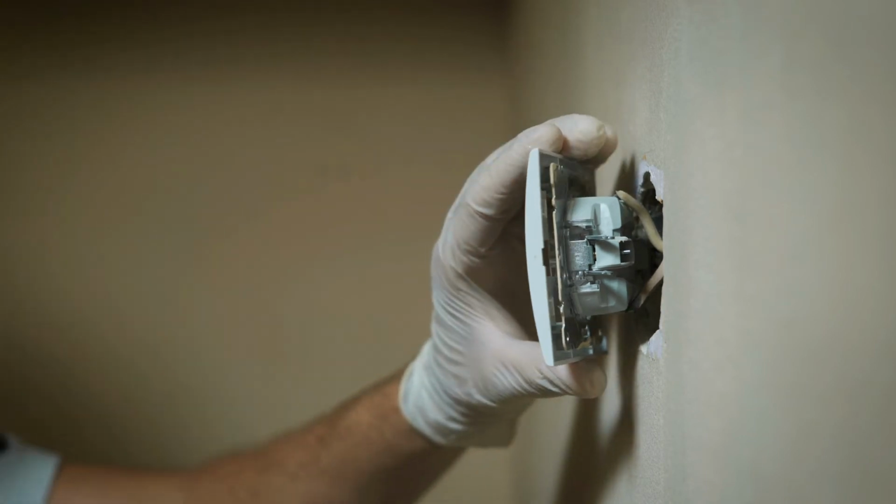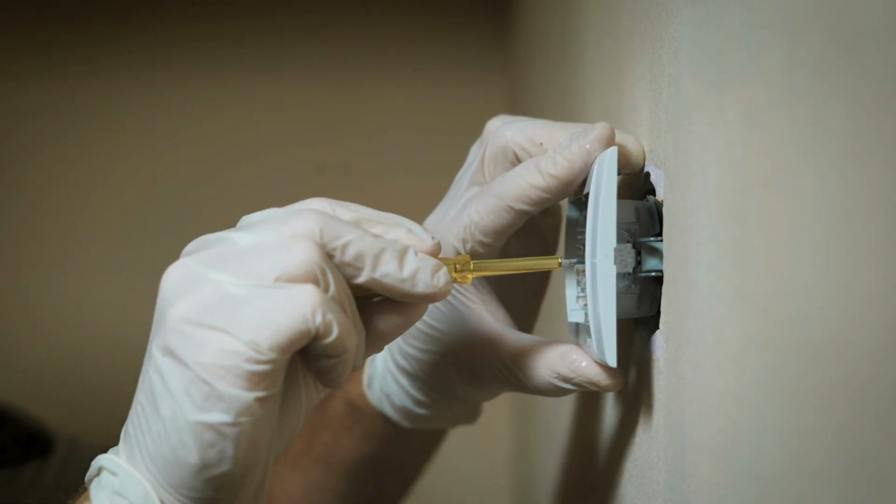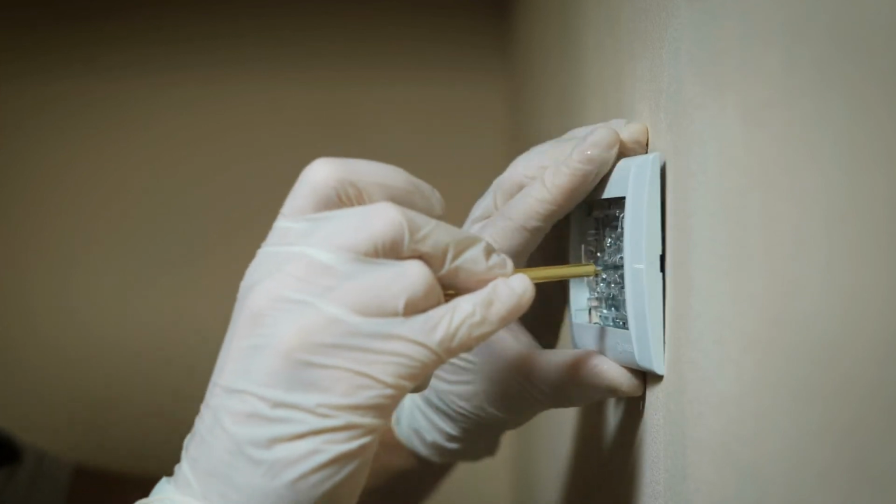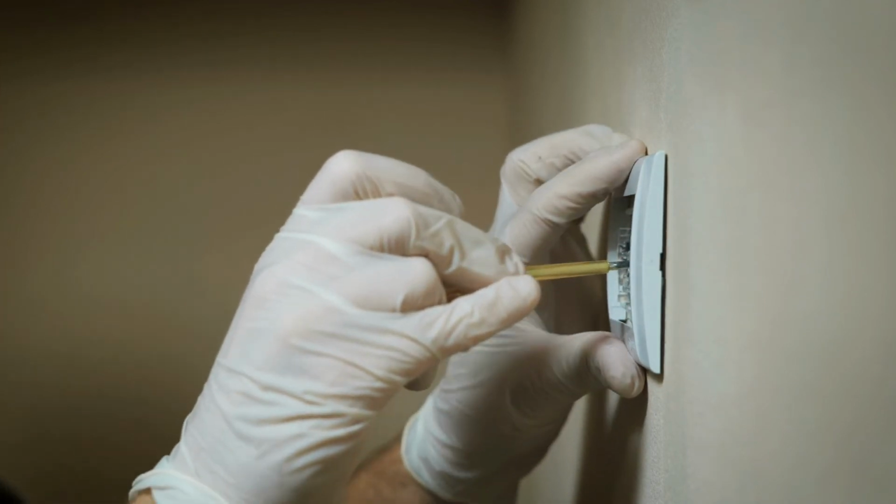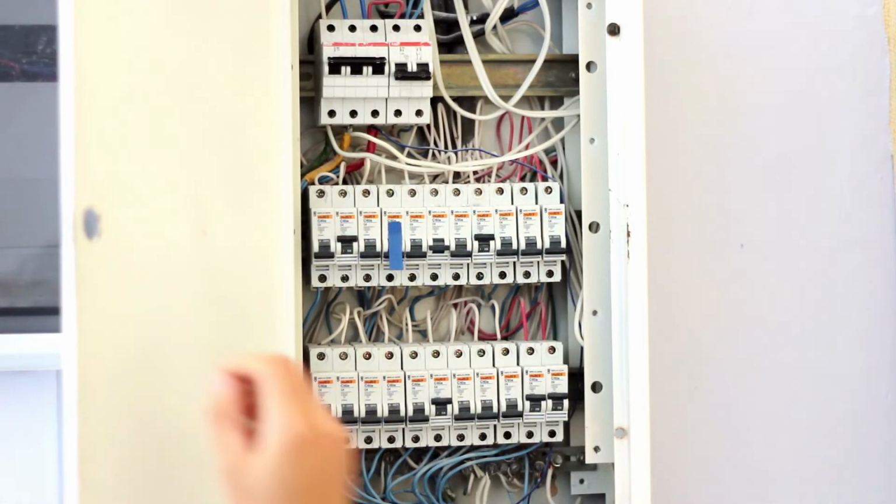So I'm curious about this, and I wonder what your answer will be. Say you identify that 5 of the plugs are not working. For electrical, what will the builder do then? Will he pull the entire line and install new lines? No, at the end of the day, it has to work. So for it to work, you can take out the faceplate and see what's happened. There may be a loose connection. There may be that the particular wire is not fitted properly. So they take it out and fit it again. If there is no supply at all, then they'll have to look at the distribution board. Then from there, if there's a problem, they look further.